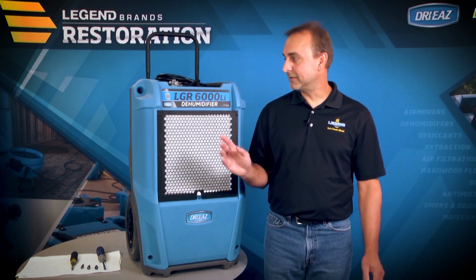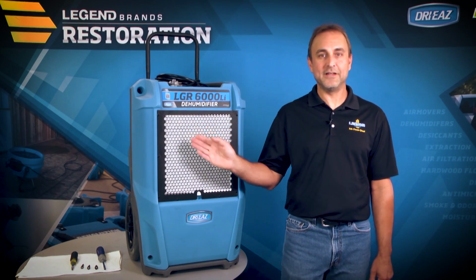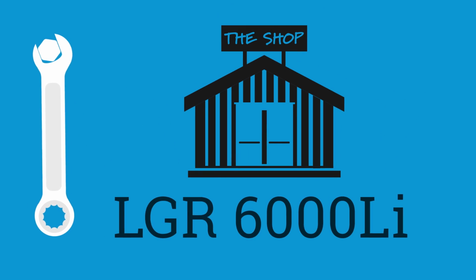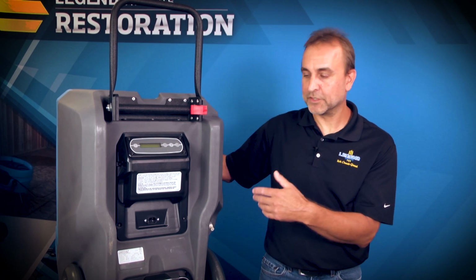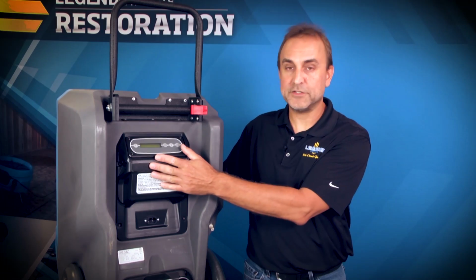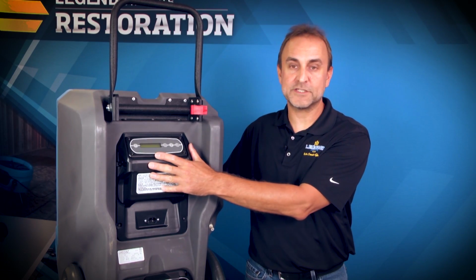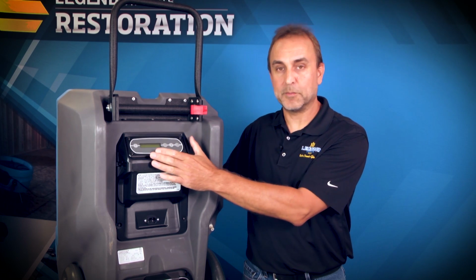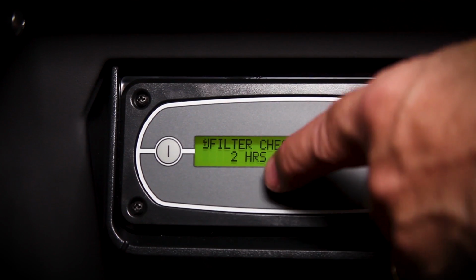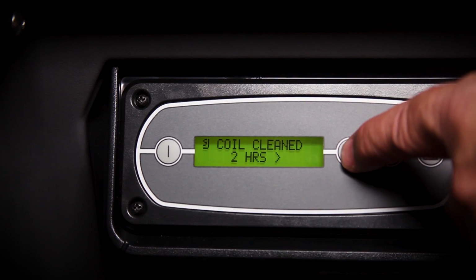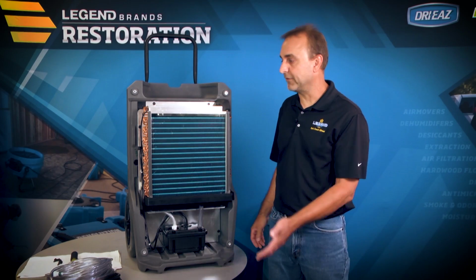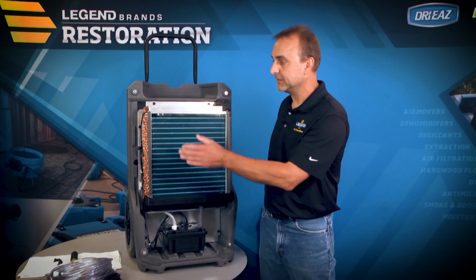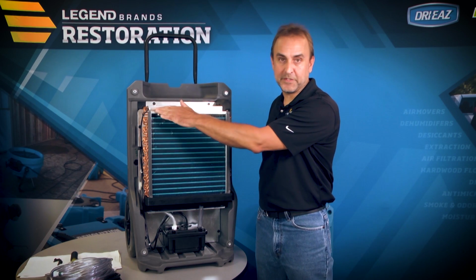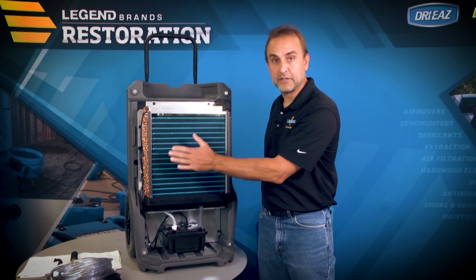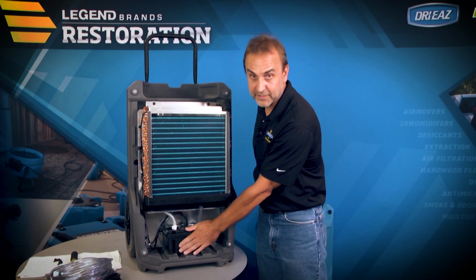I'm Richard. This is the LGR 6000 Li. Maintenance intervals are dependent upon the environment the unit is used in, but the new feature incorporated in the LGR 6000 Li, the control panel will prompt you for maintenance and cleaning of the coil and the filter. We're going to look at the three components that need maintenance. There's an inlet temperature and humidity sensor and access to it here, the coil assembly, and the condensate pump.